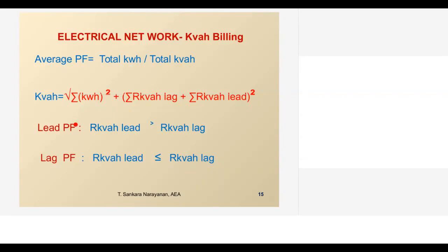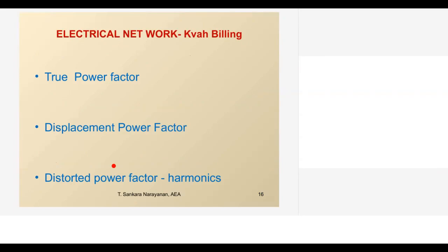So wherever kVAh billing is there, today we are monitoring true power factor. Earlier, we used to monitor displacement power factor. Today we have to monitor true power factor because the power factor varies due to harmonics. So there is a distorted power factor and a displacement power factor. True power factor, which is monitored for kVAh billing, is basically the multiplication of displacement and distortion power factor. So all the kVAh billing metering is monitoring true power factor.